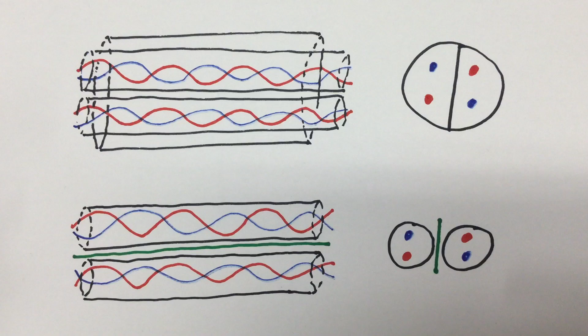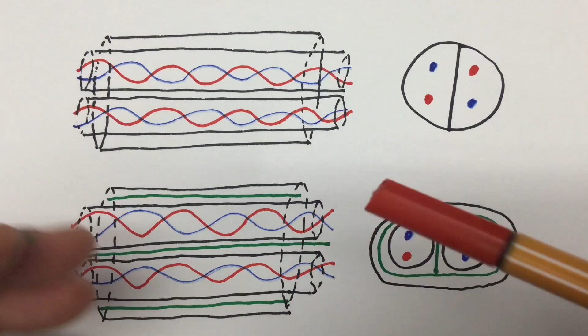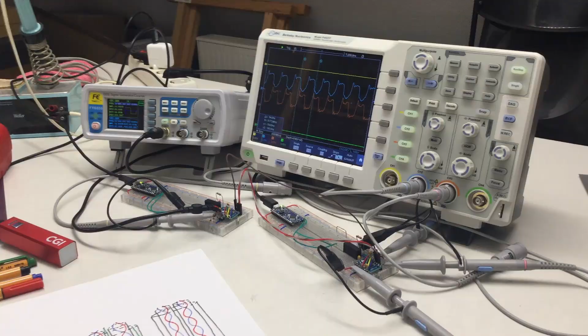There are also industrial cables available with individually shielded twisted pairs, where the shields are really electrically isolated from each other. You can also get those with a complete shield around the whole assembly, also electrically isolated - so you have the outer shield isolated from the inner shields, the inner shields isolated from each other, and inside the inner shields your twisted pairs. How to connect the different shields to which grounds or main earth - that's another topic.